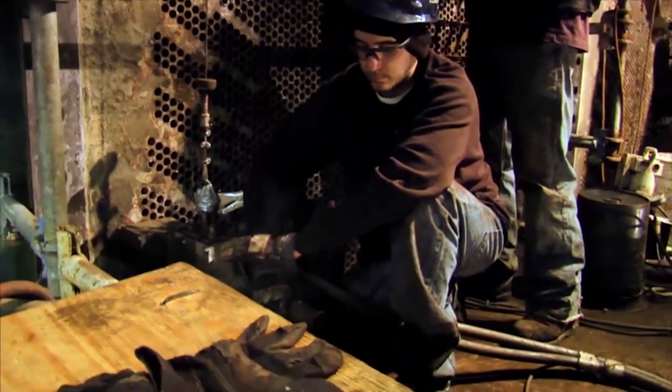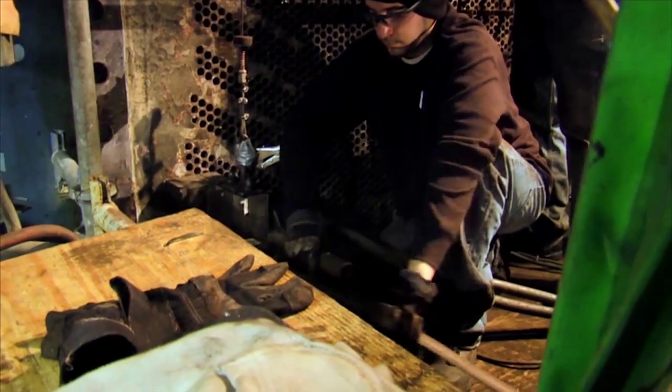If you're putting in a tube that your calculation says can only be 28 inches and you're at 45, it says the tube is going to fail. What happens as the steam is coming down from the turbine and hitting the tubes, they start to whirl. And as they whirl, they'll start to either bang against each other and cause flat spots and eventually wear through, or they'll start to spin and just break.